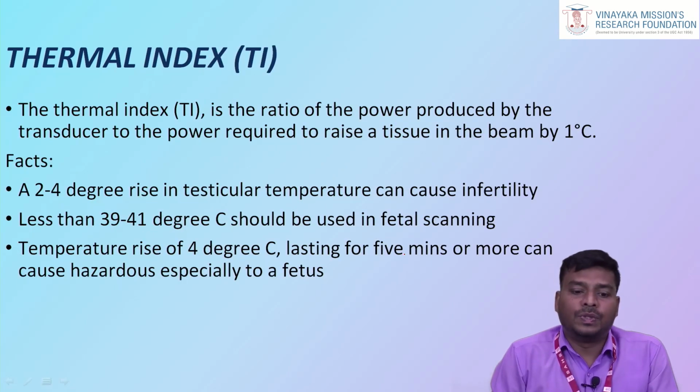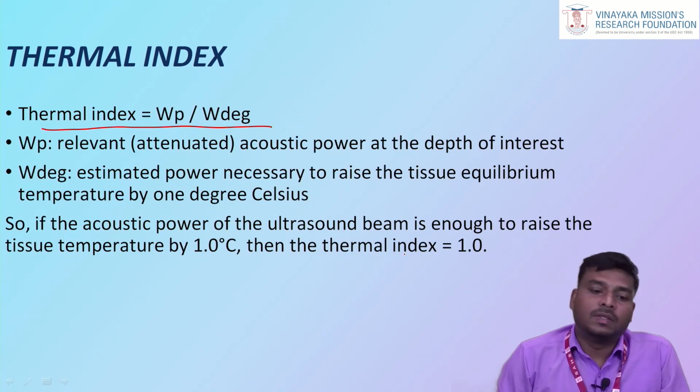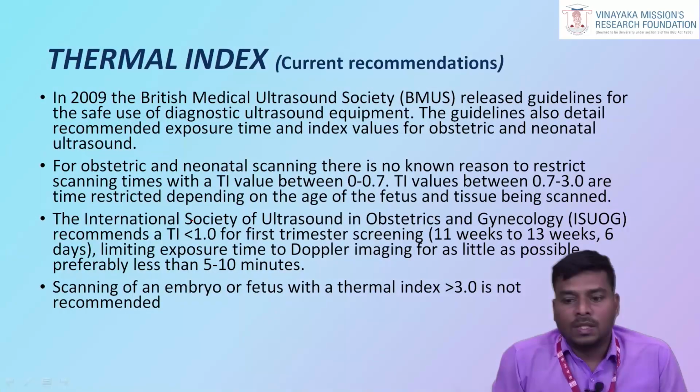A 2 to 4 degree rise in testicular temperature can cause infertility. Less than 39 to 41 degrees should be used for fetal scanning. A temperature rise of 4 degrees lasting 5 minutes or more can cause hazards, especially to the fetus. Second one, thermal index. The British Medical Ultrasound Society released guidelines.